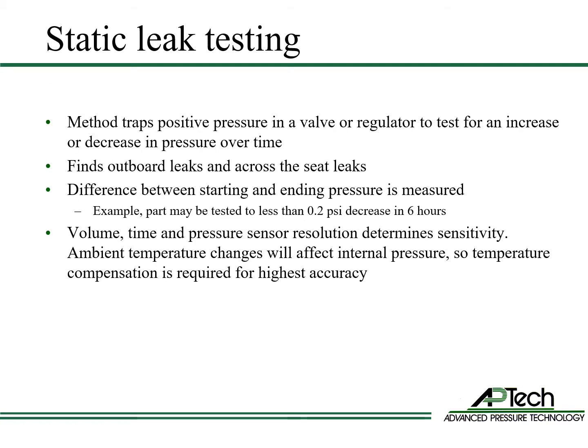The other common method of leak testing is static leak testing. It uses positive pressure to detect leaks rather than vacuum. This method traps pressure in a valve or regulator and tests for an increase or decrease in pressure over time. Static leak tests can find outboard and across-the-seat leaks. The difference between the starting and ending pressure is measured. For example, a part may be tested to less than 0.2 psi decrease in pressure over 6 hours. The trap volume, test time, and pressure sensor resolution determine the static leak test sensitivity. Ambient temperatures will have an effect on internal pressure, so temperature compensation is required for the highest accuracy.